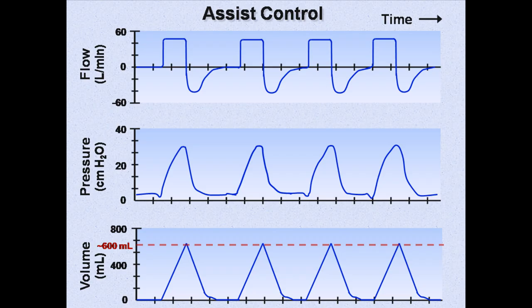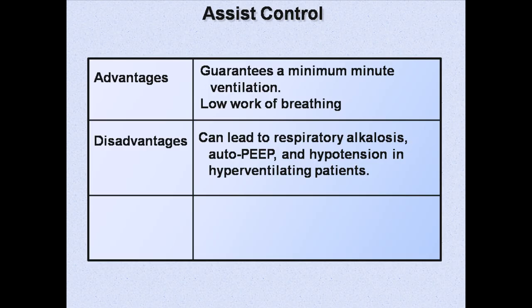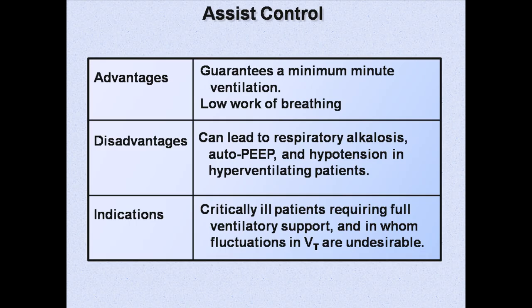You can also see that the clinician has preset the tidal volume to be about 600 milliliters. The ventilator then calculates the necessary flow rate to provide that tidal volume in the amount of time designated for each breath. Advantages of assist control are that it guarantees a minimum minute ventilation and requires low work of breathing on the part of the patient. Disadvantages are that it can lead to respiratory alkalosis, auto-PEEP, and hypotension in hyperventilating patients, because every patient-triggered breath receives a full level of support — if the rate is set to 14 and the patient suddenly breathes at 28, minute ventilation will literally double. Indications are critically ill patients requiring full vent support in whom fluctuations in tidal volume are undesirable. Assist control is overall the most commonly used vent mode in the world.